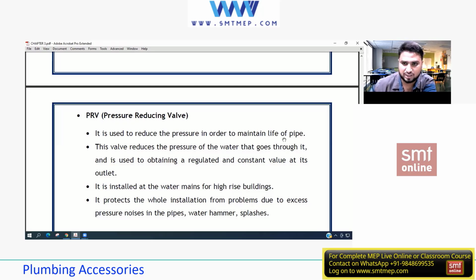If the velocity inside the pipe is higher, the life of the pipe or the material will be reduced for sure, isn't it? Yes. Now, this valve reduces the pressure of the water that passes through it and is used to obtain a regulated and constant value at its outlets. That means we have regulated the value and it's within the range, so I'm not having any problem. Constant in the sense that it is within the standard, whether I'm dealing with 80 or 60, IPC or UPC. I am pretty sure because we have done the calculation. We have fixed one PRV over here because I calculated, okay, here is 60 and here is 80. As per that I have done.